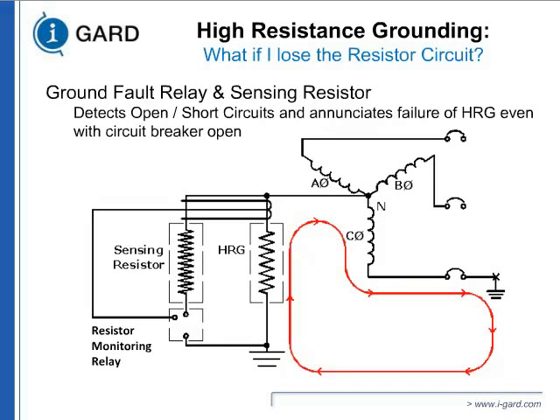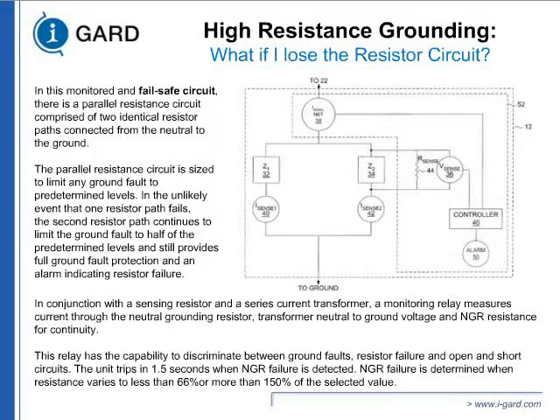Now there are people saying, okay, it gives me an alarm, I still have to shut down because I'm working ungrounded. My process is too important. I don't want to shut down. Industry responded by having two resistors in parallel. Both work continuously. If one of them fails, resistance goes up, and your current goes down and you can alarm it. That way you can know which resistor has failed and which one is still working, and now you have time to repair the resistor during a planned outage.